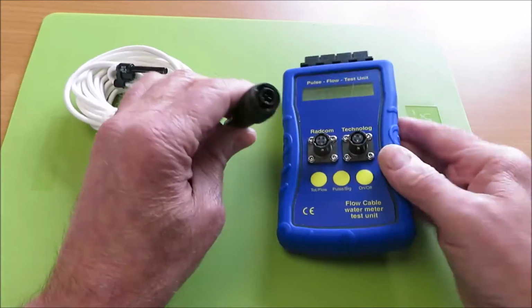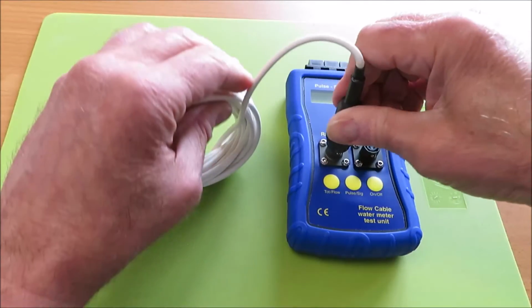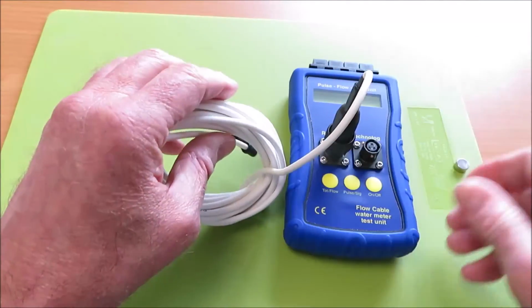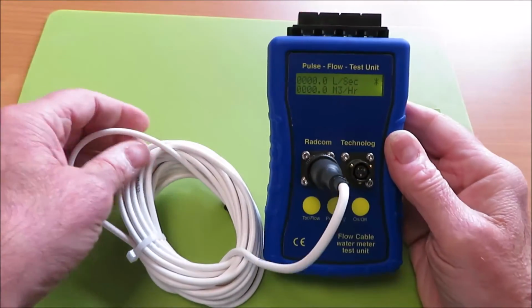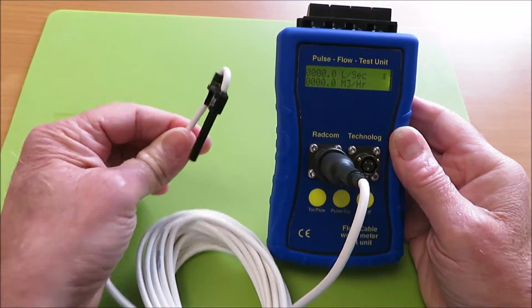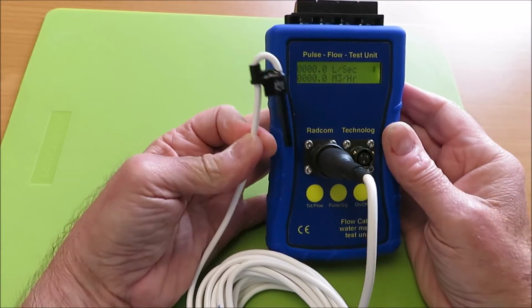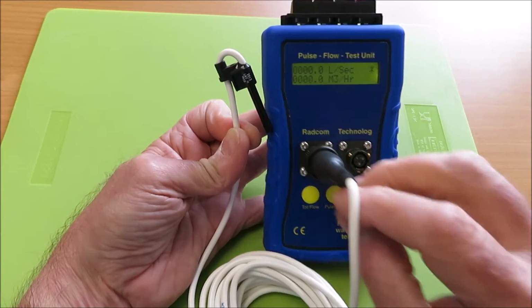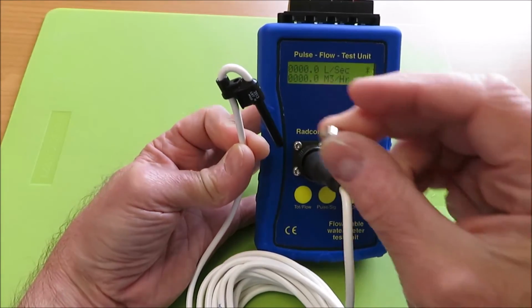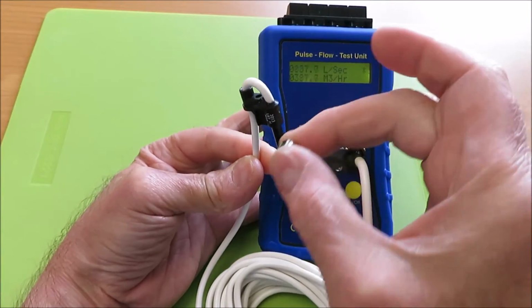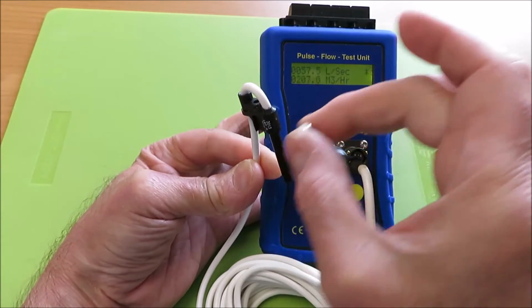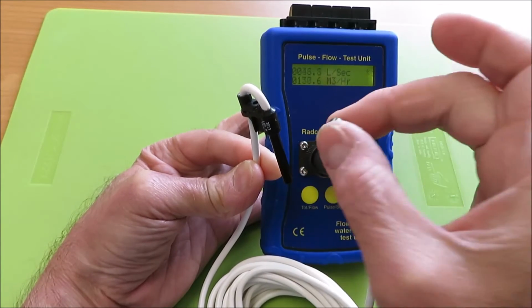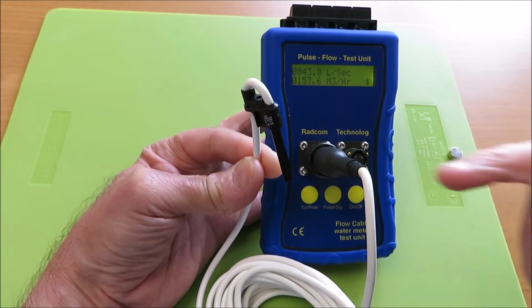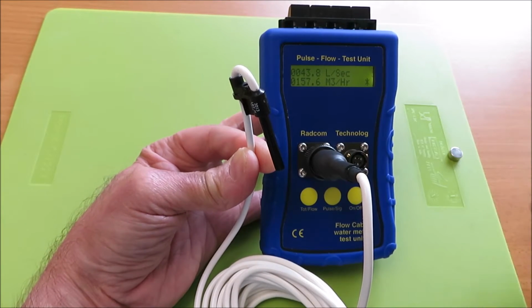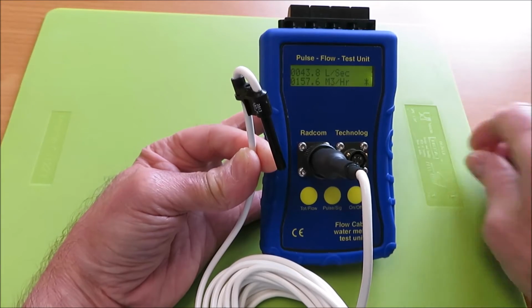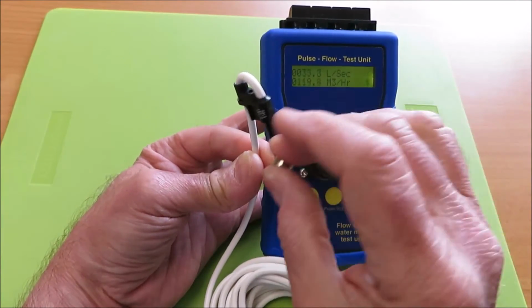But what I can do is I can connect the Radcom connector into the correct socket, just on like that. Hold that up again so that you can see the display, and again holding the T-Probe portion, if I wave the magnet in front of it, trying to do it without blocking the display, you'll see that we're getting a flow rate now, which is the magnet passing across in front of it. Basically what is in there is a reed switch which closes every time the magnet passes the sensor, and that indicates that that flow sensor is actually working.